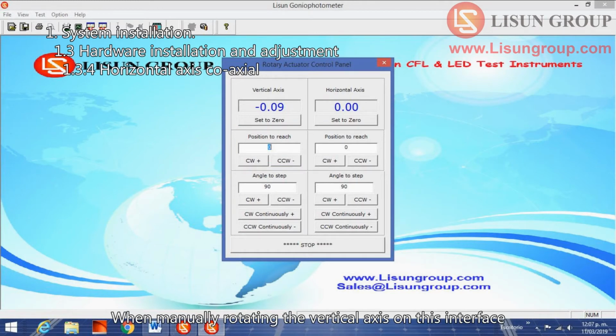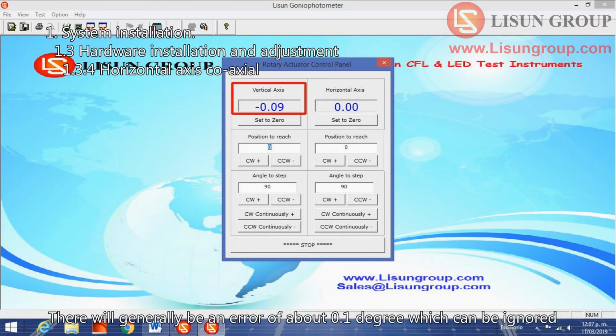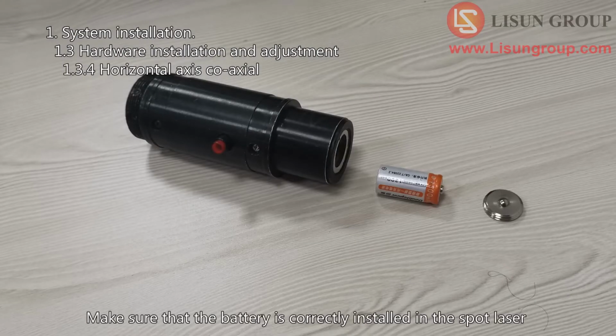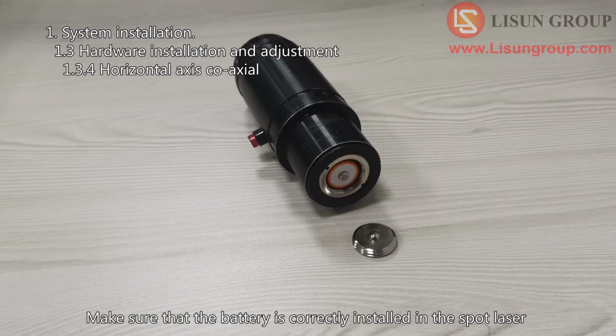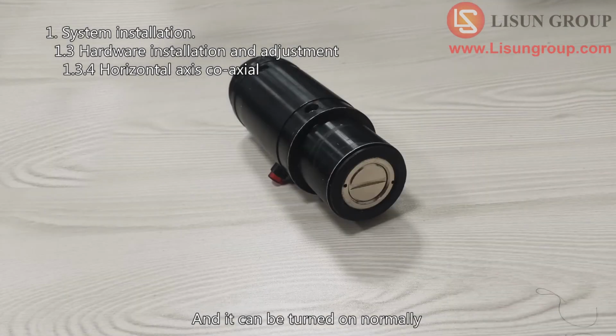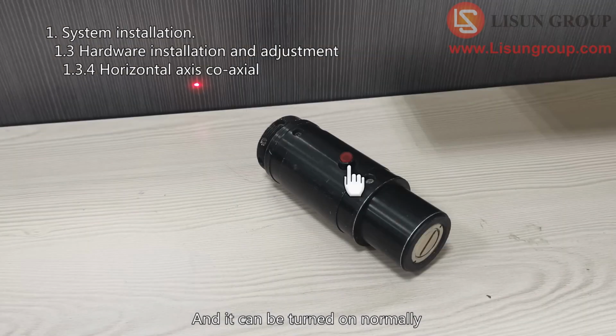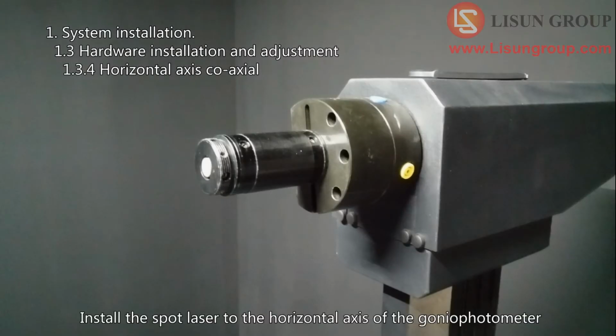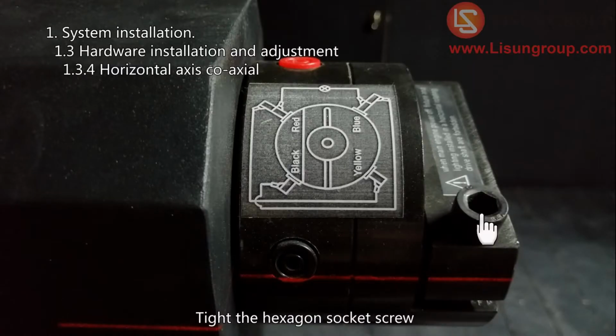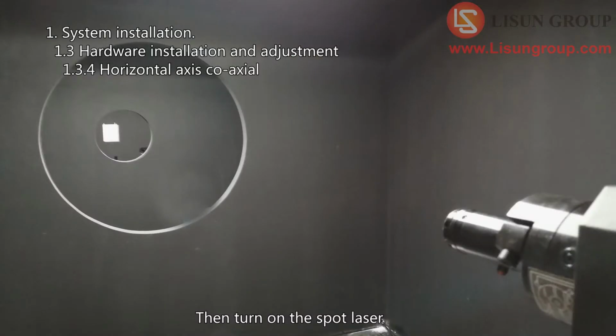When manually rotating the vertical axis on this interface, there will generally be an error of about 0.1 degree, which can be ignored. Make sure that the battery is correctly installed in the spot laser and it can be turned on normally. Install the spot laser to the horizontal axis of the goniophotometer. Tighten the hexagon socket screw. Then turn on the spot laser.